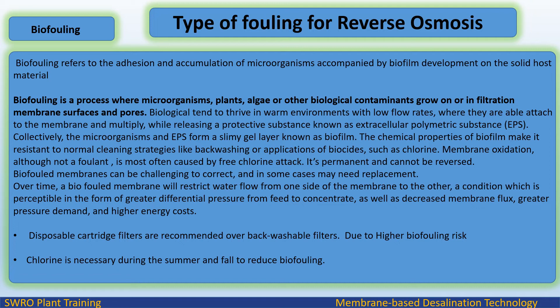Collectively, the microorganisms and EPS form a slimy gel layer known as biofilm. The chemical properties of biofilm make it resistant to normal cleaning strategies like backwashing or applications of biocides, such as chlorine. Membrane oxidation, although not a foulant, is most often caused by free chlorine attack and is permanent and cannot be reversed. Biofouled membranes can be challenging to correct, and in some cases may need replacement.